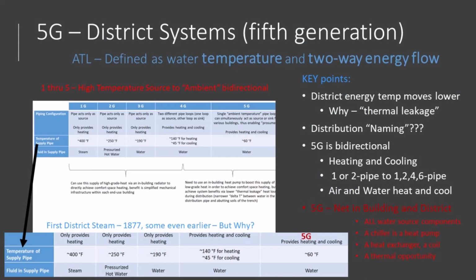How I got involved is IAPMO got involved with adding district energy systems to the code. There really isn't code that addresses what are called 5G districts. How this all got started is first generation was steam, and then gradually each district system got to cooler and cooler water temperatures, primarily because of thermal leakage, and kind of going in the opposite direction of needing really hot water so you can have big delta T's and get your GPM down.